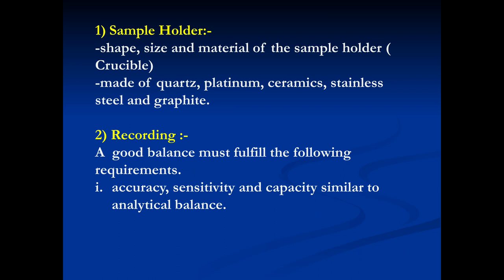The shape, size, and material of the sample holder (crucible) have an important effect on the shape of the TGA. The size and shape depend on the nature, weight of the sample, and the maximum temperature range to be used. Sample holders are made of quartz, platinum, ceramics, stainless steel, and graphite.